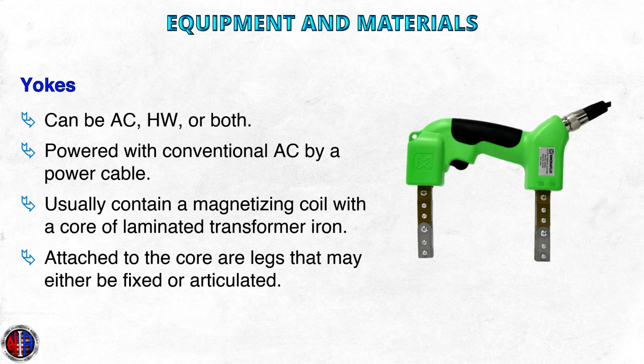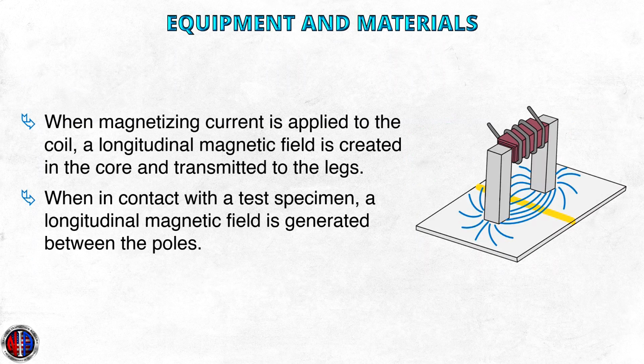Yokes. Yokes can be either alternating current, half-wave alternating current, or both, and are generally powered with conventional AC by a power cable. Some yokes can be powered with a battery. Yokes usually contain a magnetizing coil with a core of laminated transformer iron. Attached to the core are legs that may be either fixed or articulated. When magnetizing current is applied to the coil, a longitudinal magnetic field is created in the core and transmitted to the legs. When in contact with the test specimen, a longitudinal magnetic field is generated between the poles.